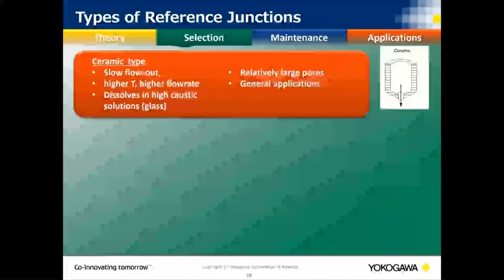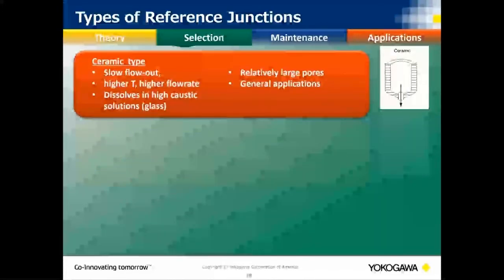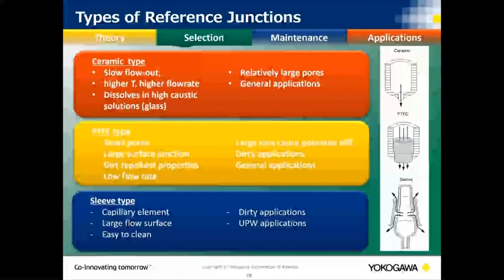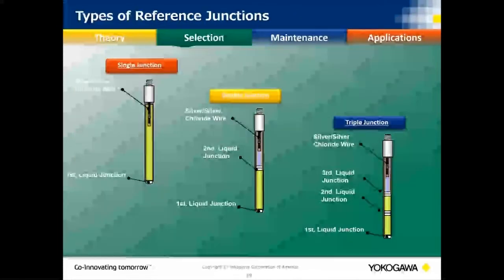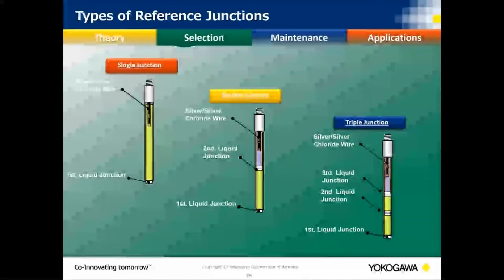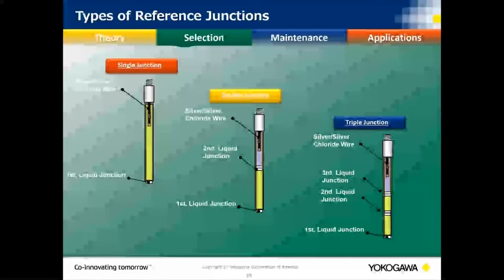Junction selection matters as discussed in pH. Manufacturers offer ceramic, Teflon, and sleeve junctions. For general purpose or batch neutralization ORP, you can usually use Teflon or ceramic. For really dirty applications or ultra-pure water, you'll want a sleeve-type junction to get the longest life out of your electrodes.